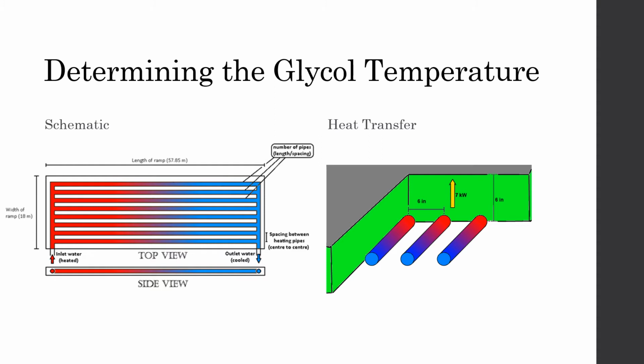Using these values, a shape factor was calculated and was used in combination with the thermal resistance of the pipe and concrete material to determine the required temperature of the glycol. This value was determined to be slightly over 12 degrees Celsius and required a mass flow rate of 0.20 kilograms per second to constantly maintain the required temperature.